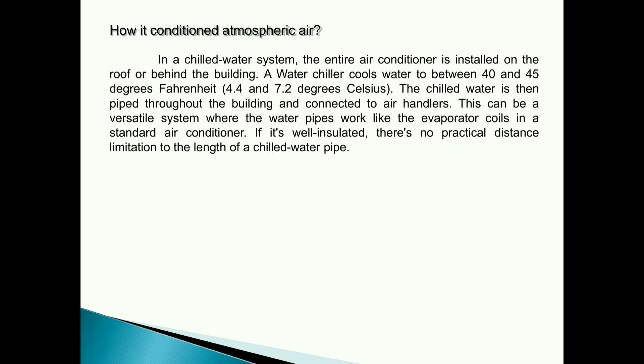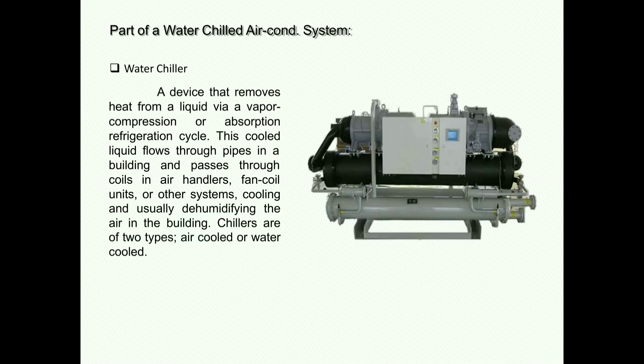In a chilled water system, the entire air conditioner is installed on the roof or behind the building. A water chiller cools water to between 40 and 45 degrees Fahrenheit, or 4.4 and 7.2 degrees Celsius. The chilled water is then piped throughout the building and connected to air handlers. This can be a versatile system where the water pipes work like the evaporator coils in a standard air conditioner. If it's well insulated, there's no practical distance limitation to the length of a chilled water pipe.